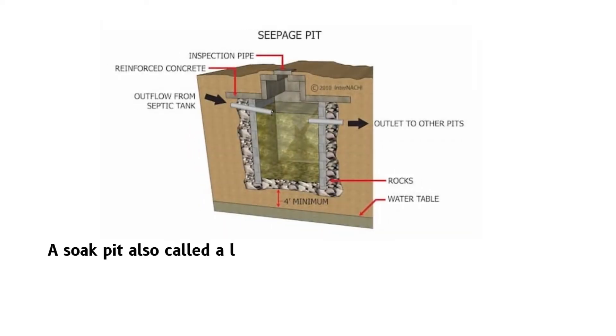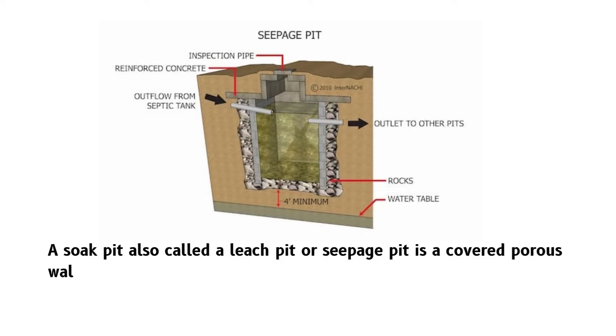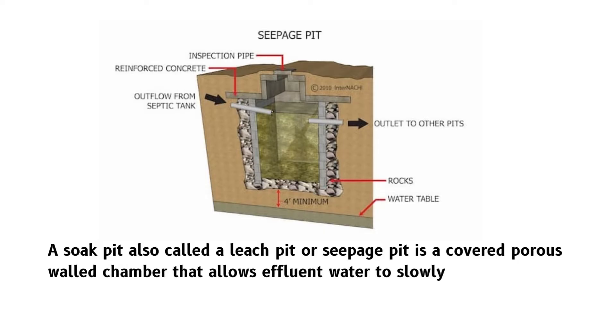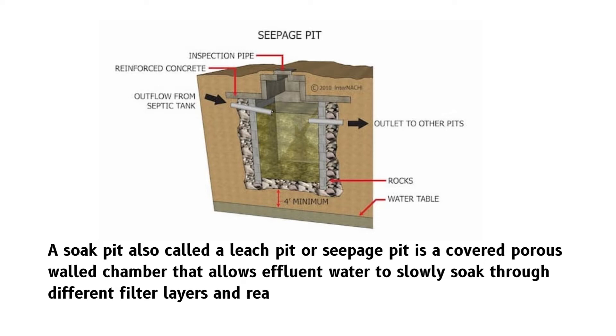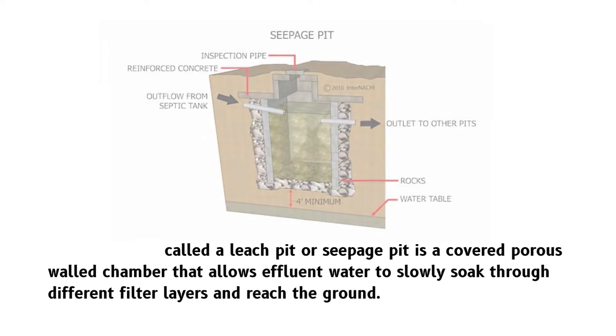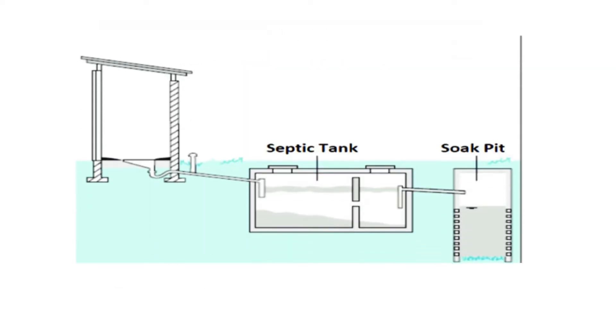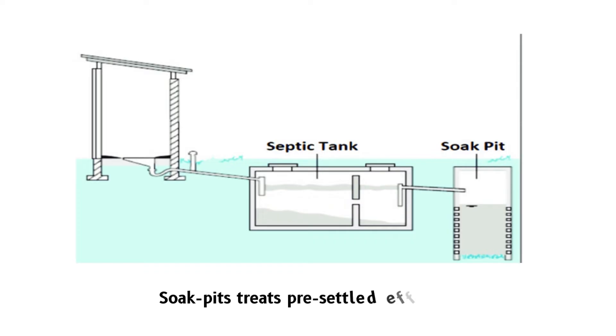A soak pit, also called a leach pit or seepage pit, is a covered porous walled chamber that allows effluent water to slowly soak through different filter layers and reach the ground. A soak pit chamber receives the effluent coming out from a primary treatment plant like a septic tank, aerobic treatment system, etc. Hence, it partially treats a pre-settled effluent.